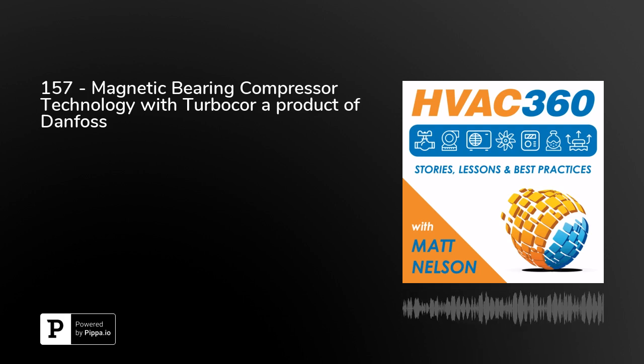The other issue to consider is that our compressors do not incur any mechanical degradation over the life of the compressor. With traditional screw compressors, it's very common to see significant mechanical wear after extended periods of operation. In fact, several OEMs who manufacture screw compressors offer renewal programs to overhaul them in order to alleviate that issue. They'll rebuild the compressor, replacing the parts that come into contact with each other, to get the performance you got when the compressor was brand new.